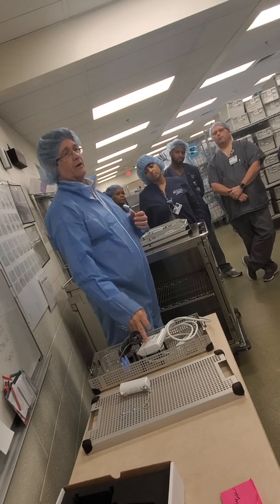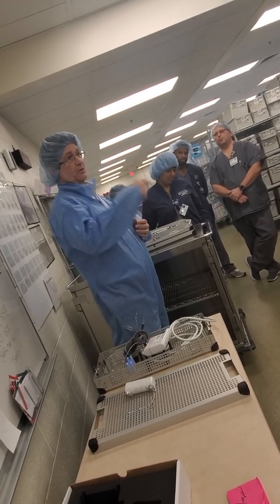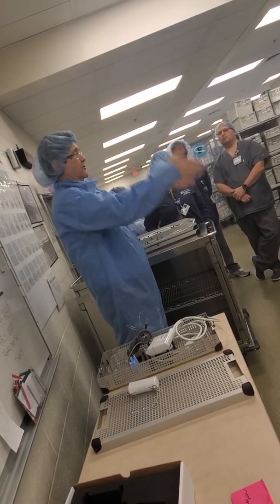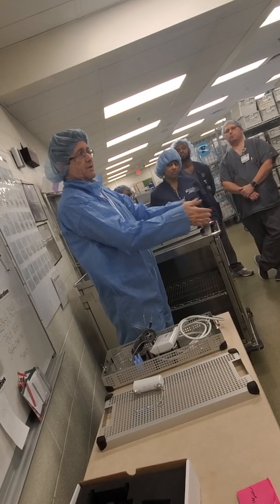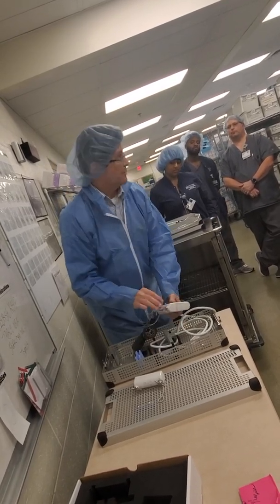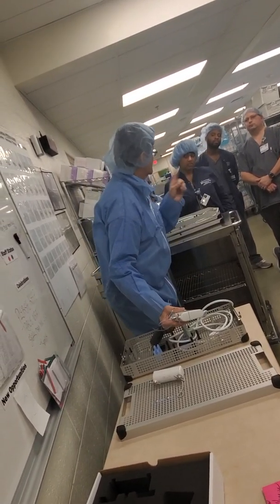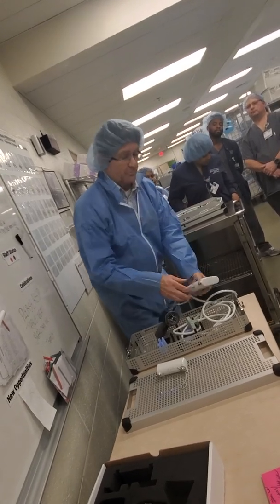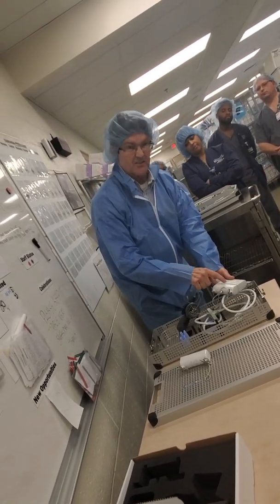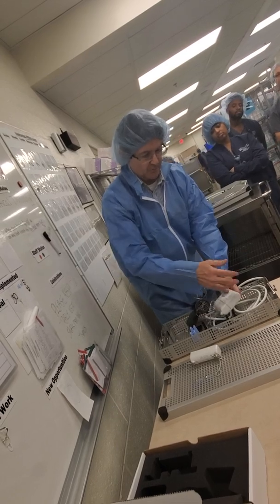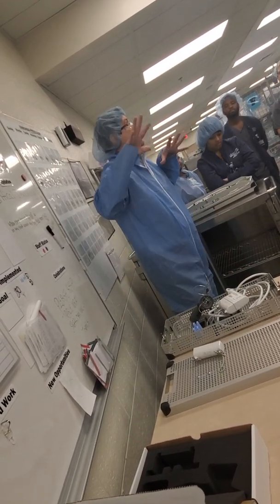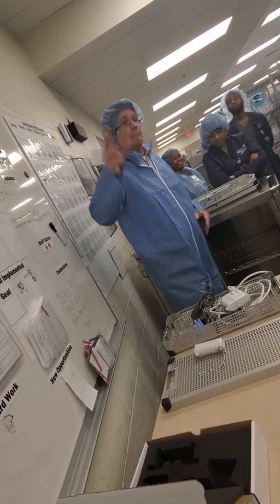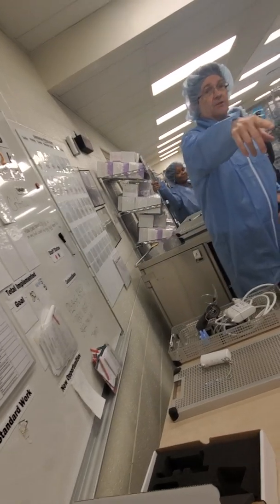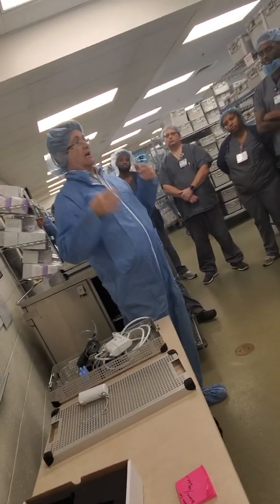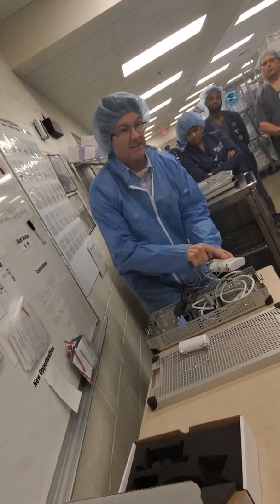If the cap was on that one and you put it in Sterrad, remember, the first is pressure. The pressure, remember, this is waterproof. It's not gas proof. So the pressure goes up, it goes inside and pressurizes the probe, the plug, the cord, and the probe. But later, there's negative pressure. And all of the stuff comes out. It doesn't come out here.